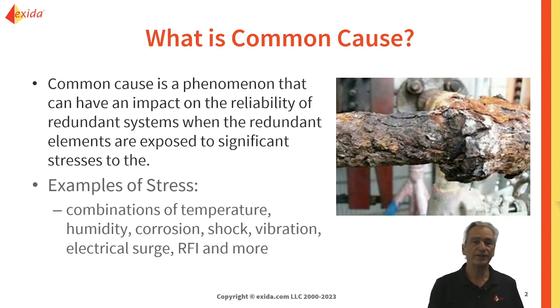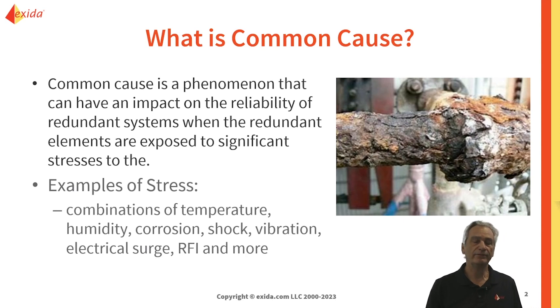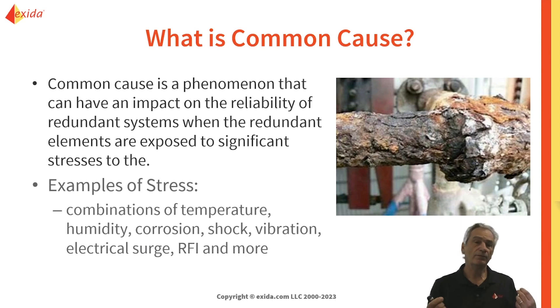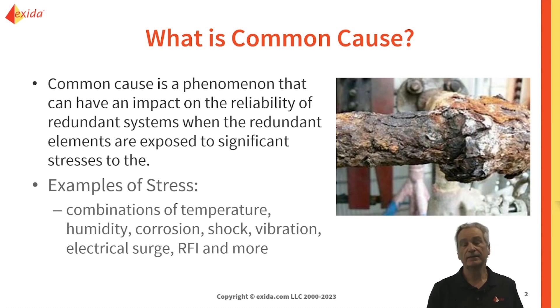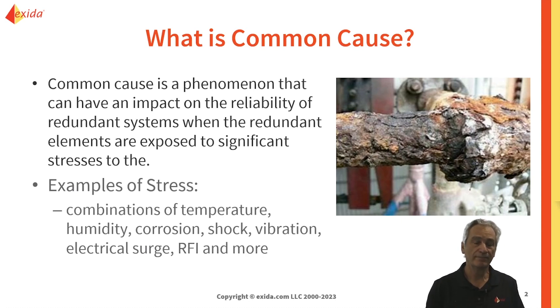So first and foremost, what is common cause all about? A common cause is a phenomenon that can affect redundant systems. Usually with redundant systems they're the same manufacturer's devices — just two of them or three of them, however many we have. If we have external stresses such as excessive heat, vibration, RFI, humidity, and so on, this can affect the redundant systems in similar ways, and therefore we have to take that into consideration when we're doing our calculations for our PFD average.